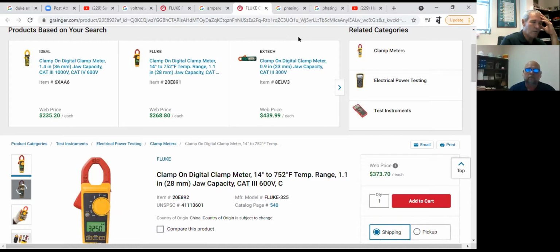This will go around a fuse barrel, it'll go right around it. I can actually check the amperage through a fuse, I can put it right around the conductor. So now we're figuring out, well, how do I get that reading? This is what you clamp on. Obviously, you've got to use rubber gloves, and you've got to be in an insulated device to do it.